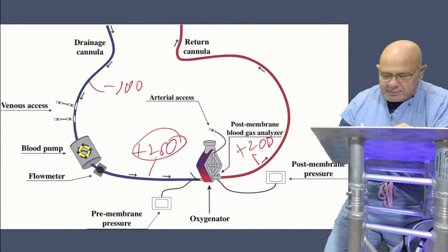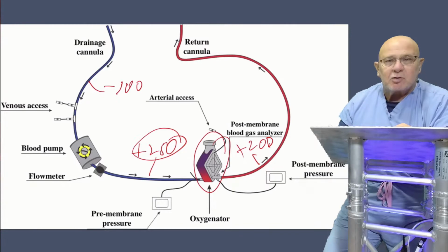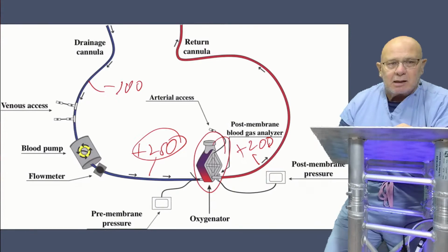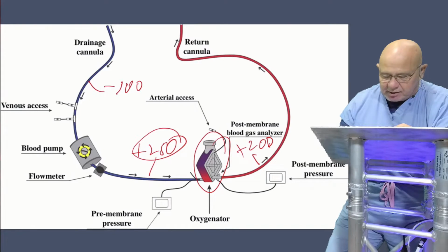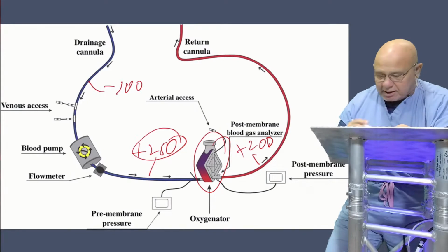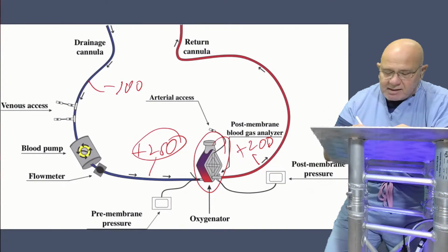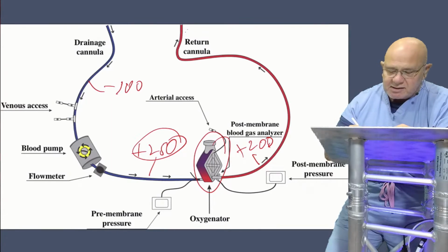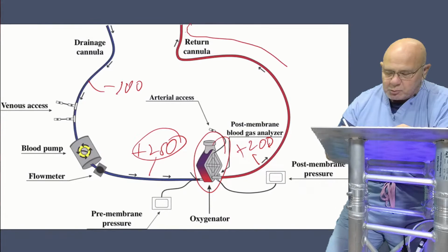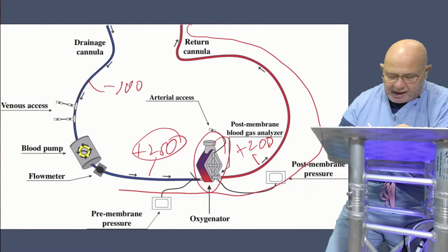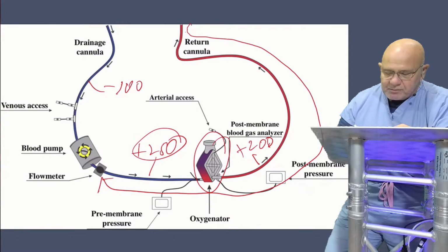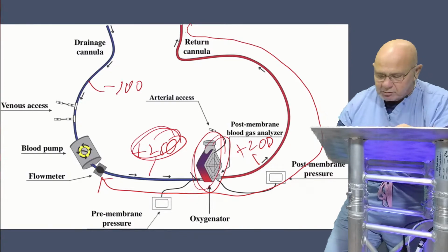So normally speaking, you're going to have a delta P across any hollow fiber membrane oxygenator or microporous hollow fiber oxygenator, as the case may be. And then, of course, your return cannula will be your final point of resistance, and that pressure would be reflected all the way back to here. So it's that pressure plus the resistance here gives you this number here. Okay, so great.